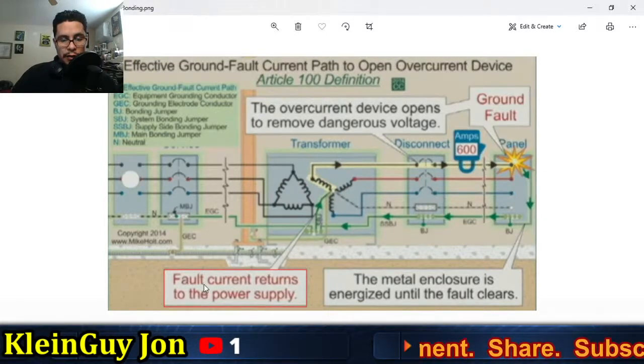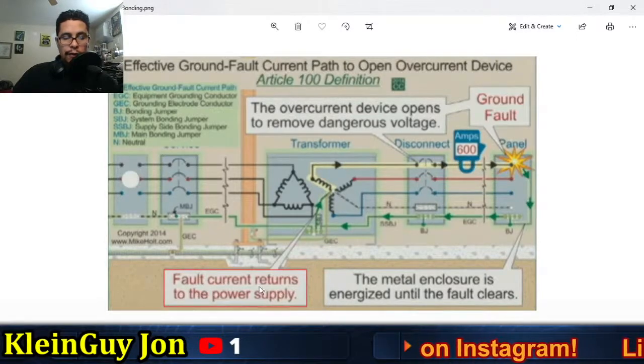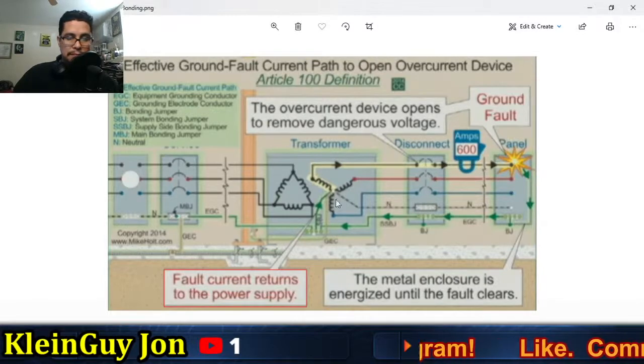So now you can see here, it says the fault current returns to the power supply when there is a ground fault. The overcurrent device opens to remove dangerous voltage. The metal enclosure is energized until the fault clears. So you can see right here, fault, energized equipment. Right there, back to the source. Fault current returns to the power supply. Then the breaker trips. And that's it.